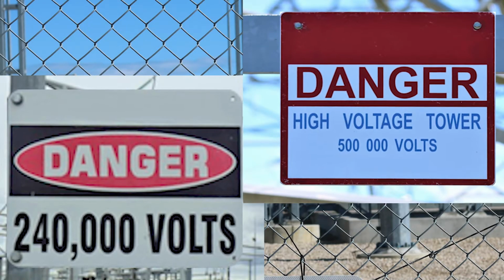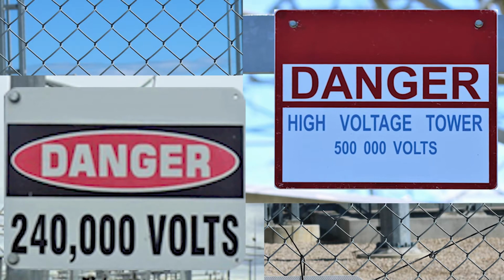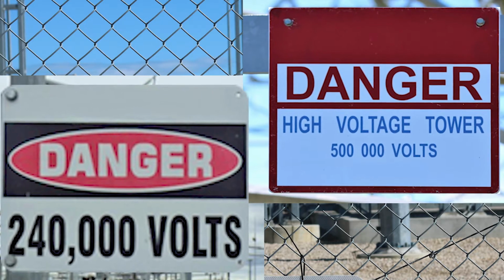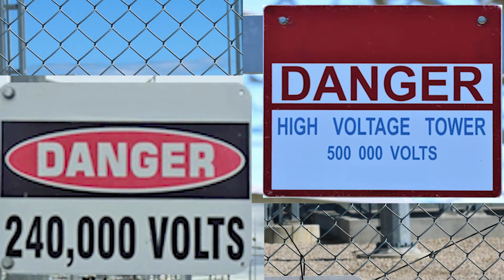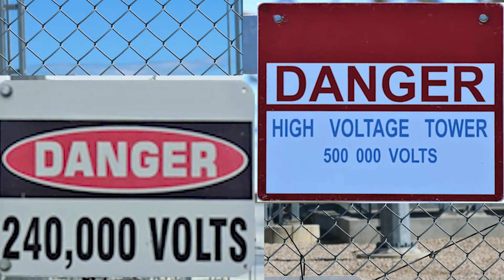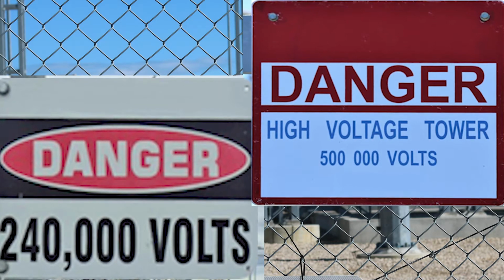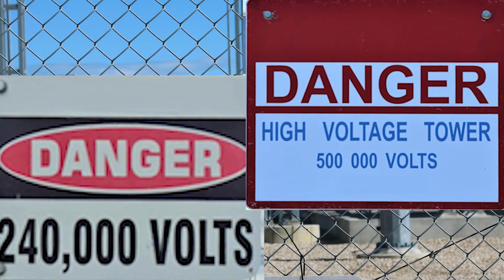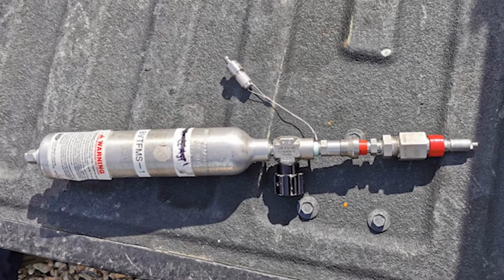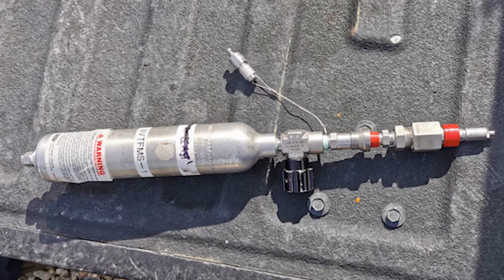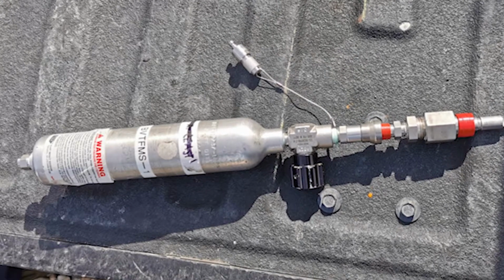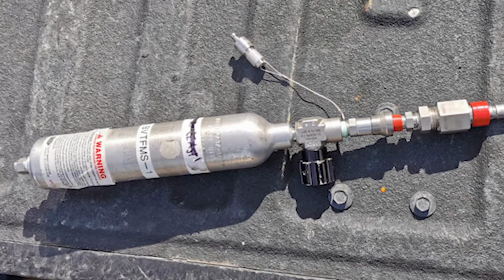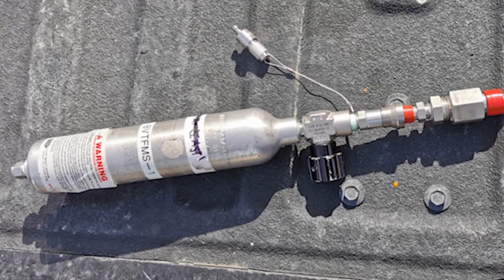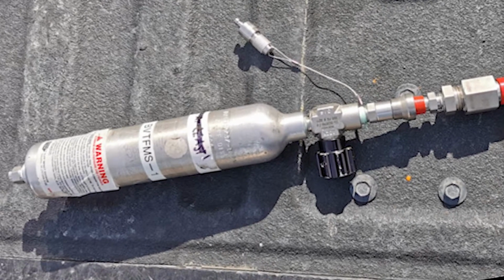Maintaining limits of approach is critical. We were escorted in, we attended their safety briefing prior to work beginning, and we followed all of their safety protocols. These cameras allow us to work outside our limits of approach and keep our people safe. Prior to beginning the inspection, we first confirmed that we had all the correct settings on the camera and ensured that we were able to detect the gas. We conducted a bump test with a small canister of SF6 gas.